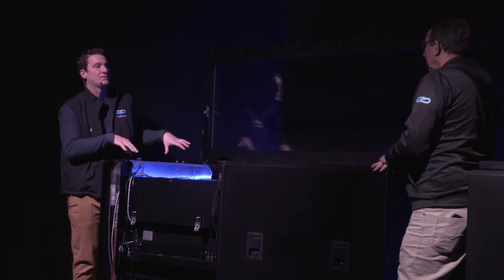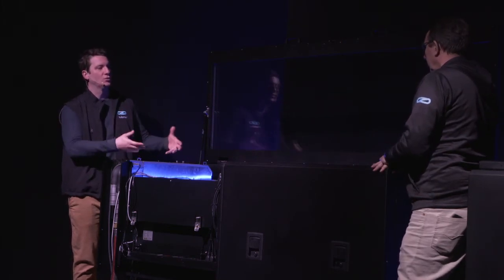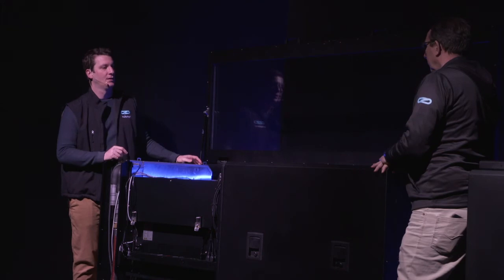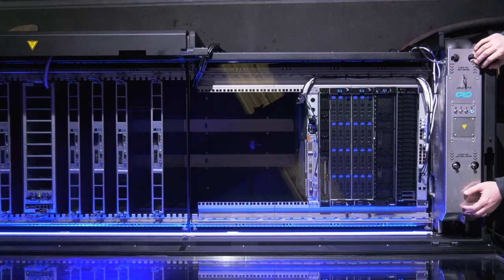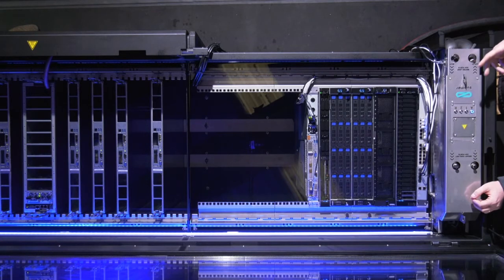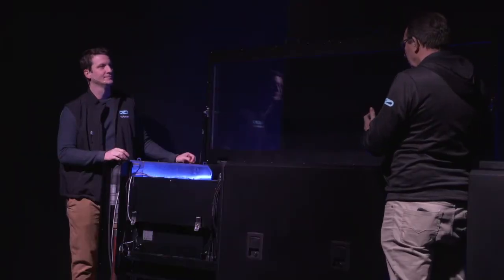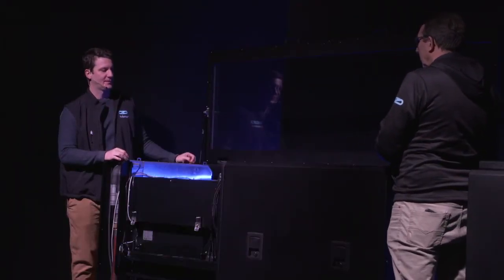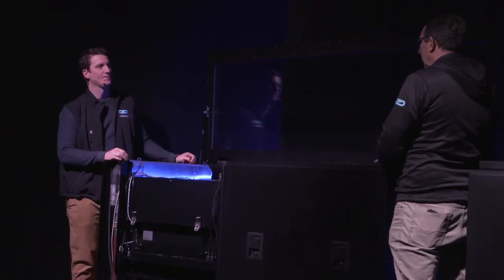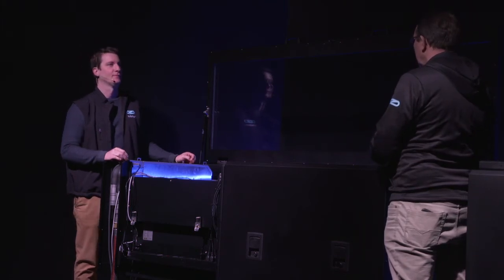And of course, the CDU is fully submerged in the liquid. It's cooled by the liquid itself. So all the electronics that are in a CDU are leveraging immersion cooling technology themselves. That's how much we trust our liquid, that we even run our CDUs in it. So Daniel, now whenever we disconnect the water loop, the temperature in the tank will rise. How long will it take before the servers start switching down?